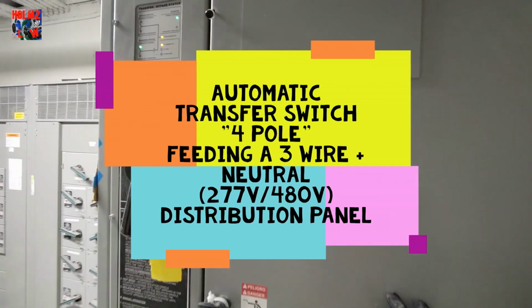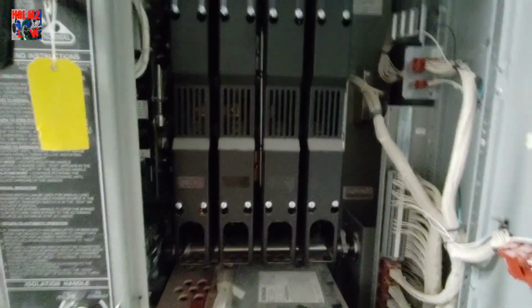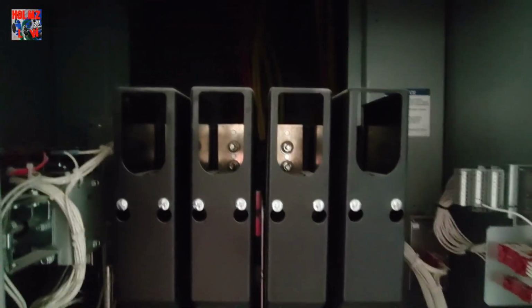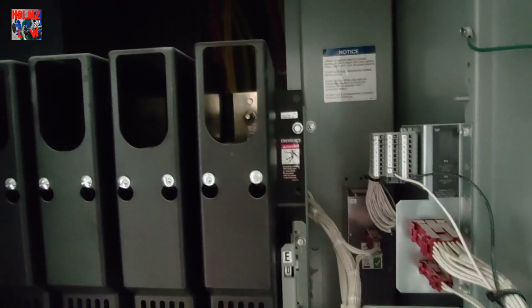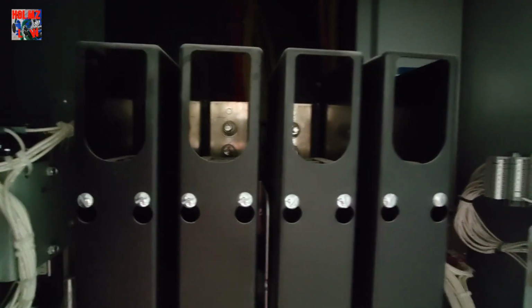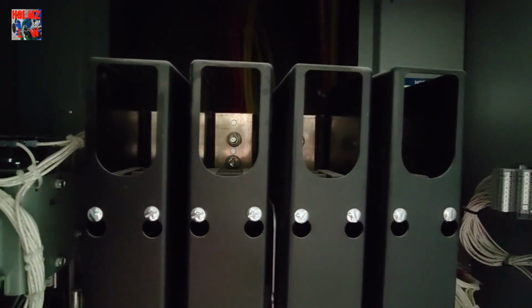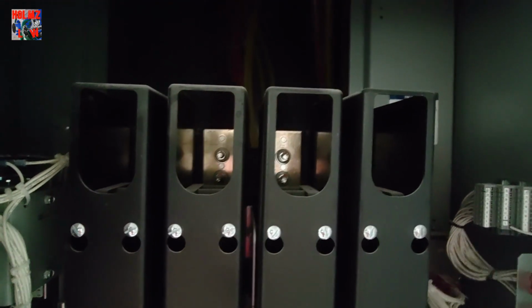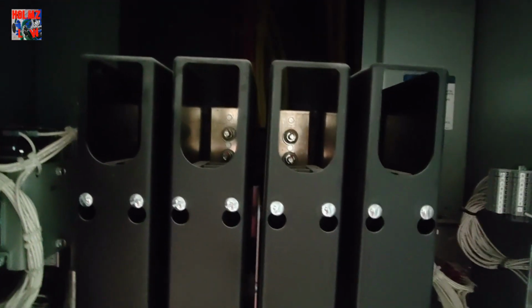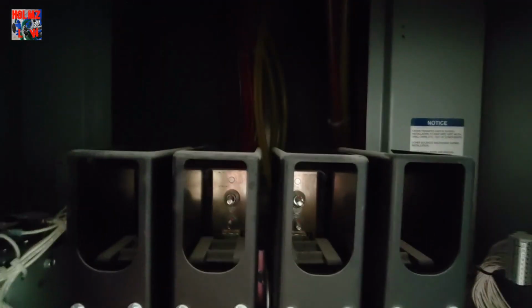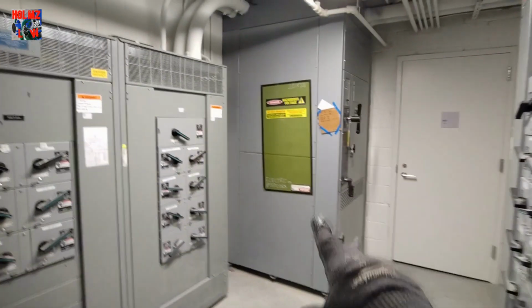This here is the ATS. This is an automatic transfer switch to one of the loads. This is actually working the optional standby loads. As you can see, it's a four-pole switch, three of the phases and the neutral. And that's what we have to have in order to have a generator that's going to be bonded or, you know, separately derived and whatnot. Yep. Four-pole switch. So that's the whole ATS there.